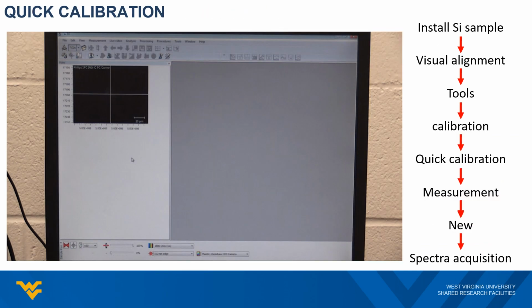Now we know how to perform a Raman measurement, but before measuring your own sample, you should always start with a silicon calibration sample to run a quick calibration, then confirm the performance of the spectrometer. Similar to other samples, you will need to load the silicon sample under the microscope, then perform the visual alignment using 50 times objective. Once you have the silicon sample aligned, go to Tools tab, choose Calibration, then choose Quick Calibration. The system will ask for confirmation of the sample alignment. Just confirm it, and it will start the quick calibration.